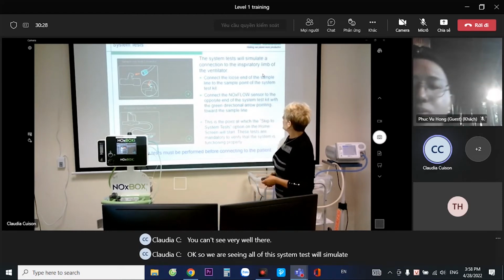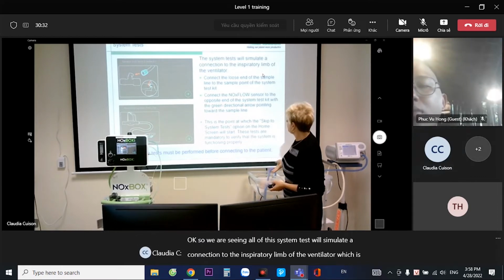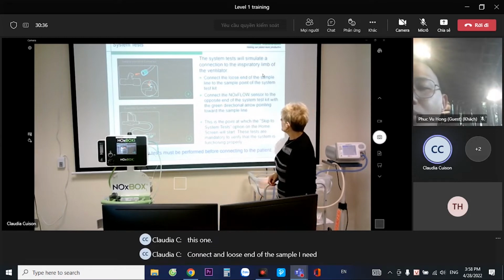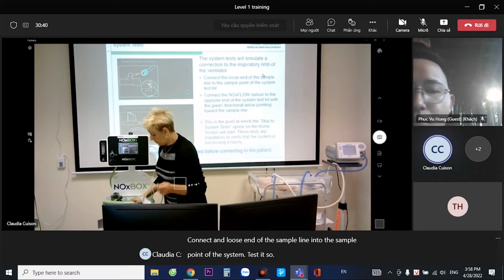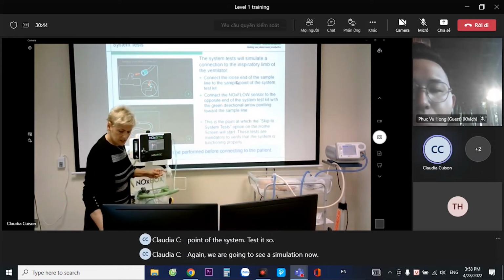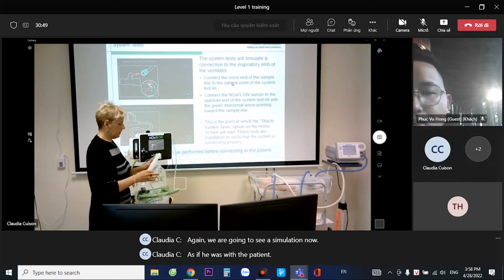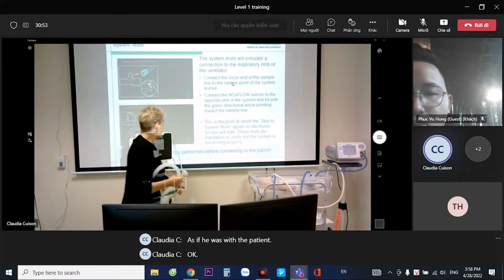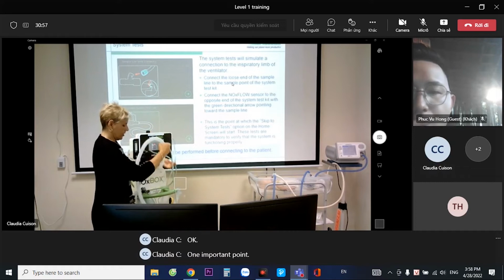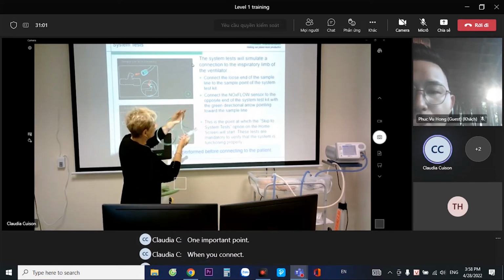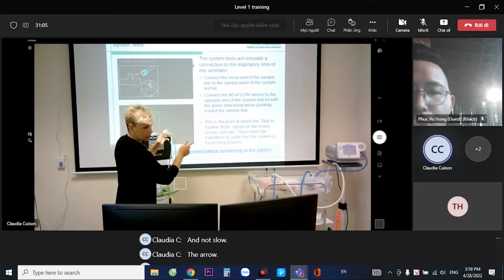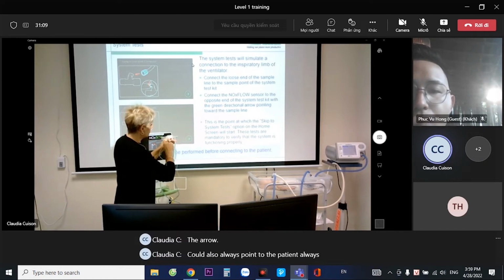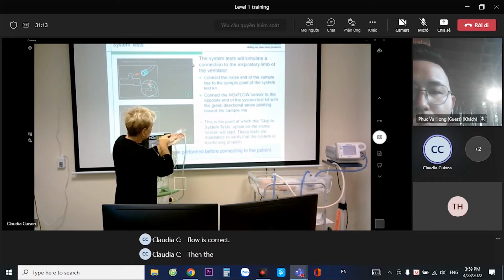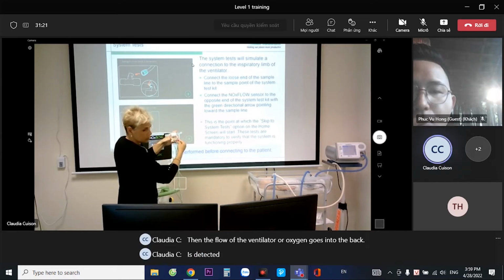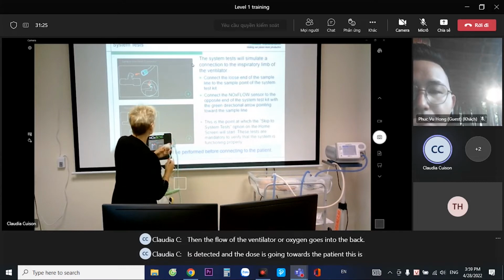System test will simulate a connection to the inspiratory limb of the ventilator, which is this one. Connect the loose end of the sample line into the sample point of the system test kit. So again, we are going to see a simulation now, as if it was with the patient. Okay. One important point, when you connect the NOxFLOW, the arrow should also always point to the patient, always, right? So the flow is correct. Then the flow of the ventilator or oxygen goes into the back, is detected, and the dose is going towards the patient. This is very important.